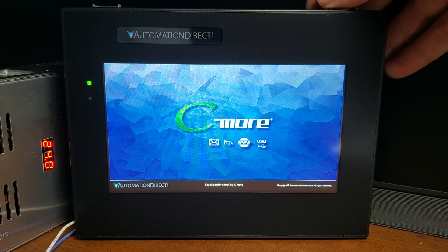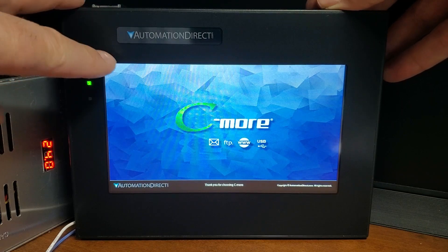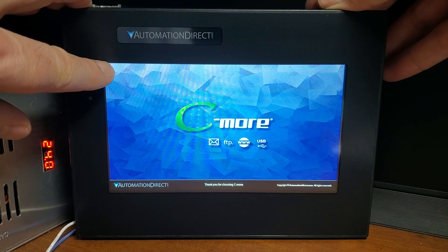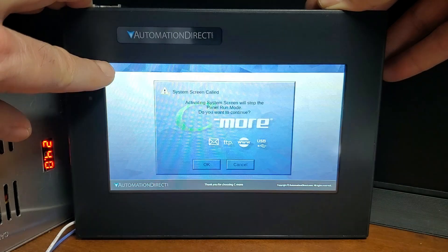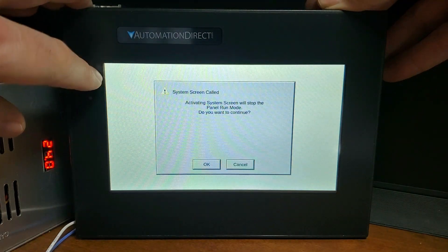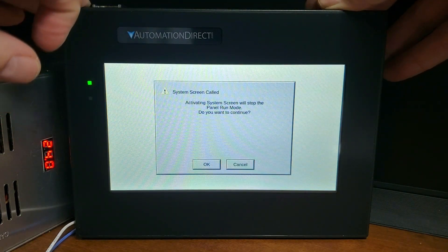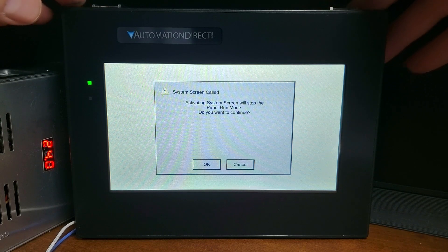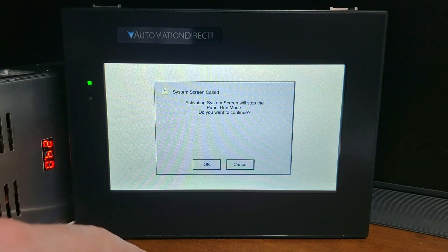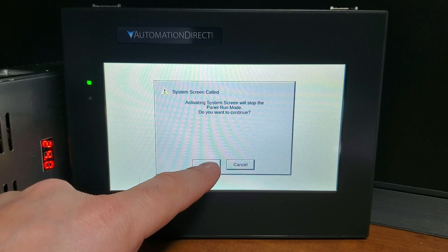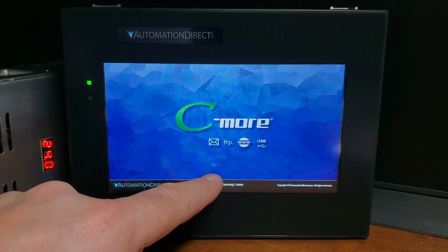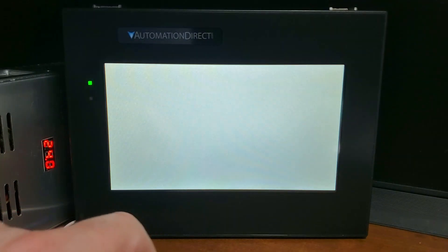Accessing the C-more system setup screens: press the upper left corner of the panel display area for 3 seconds and the main menu will be displayed. If a program is loaded into the C-more HMI, a warning message will appear telling you that activating system screens will stop the panel mode from running. You have a choice to continue — select OK to continue and the system setup menu screen will now appear.